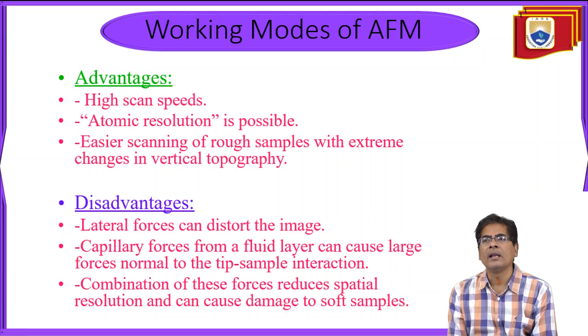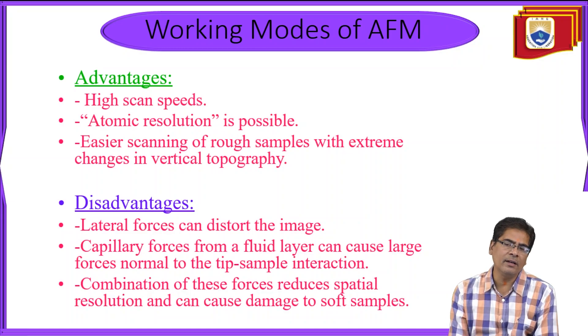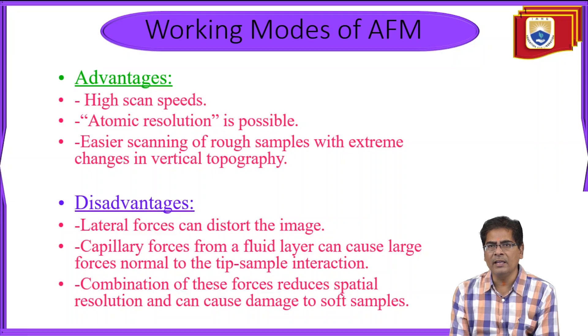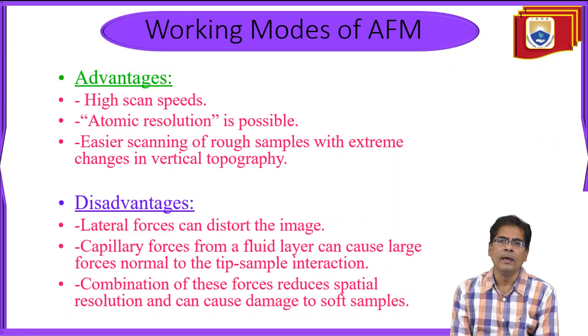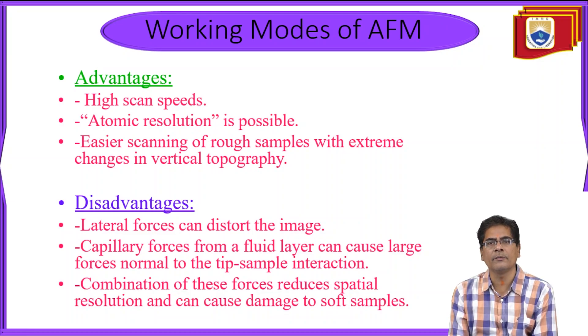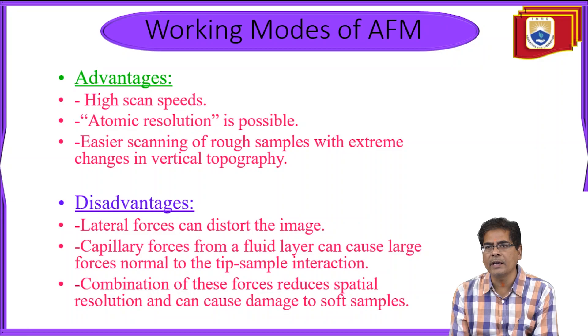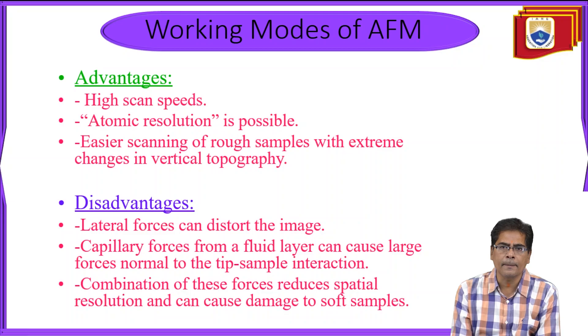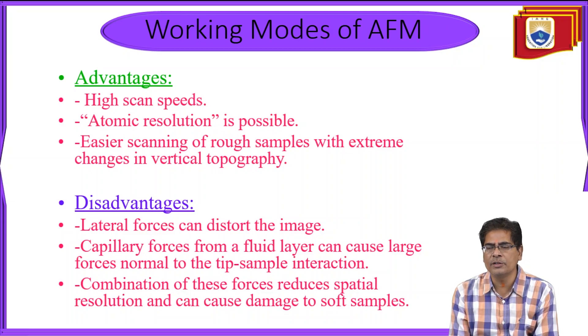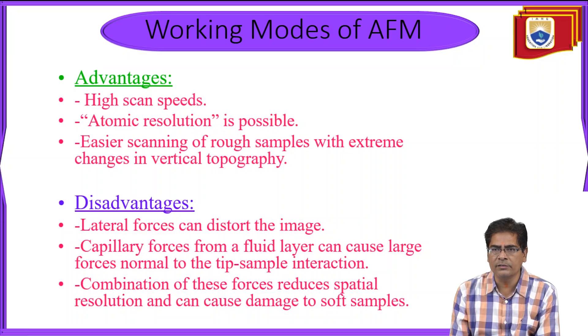Contact mode advantages include high scan speeds, atomic resolution is possible, and easier scanning of rough samples with extreme changes in vertical topography. Disadvantages include that lateral forces can distort the image, capillary forces from a fluid layer can cause large forces normal to the tip-sample interaction, and the combination of these forces reduces spatial resolution and can cause damage to soft samples.